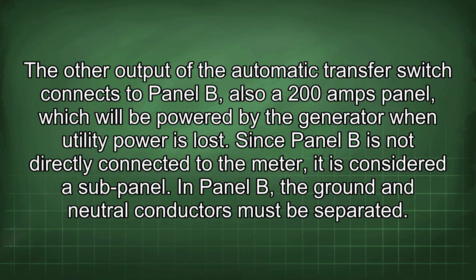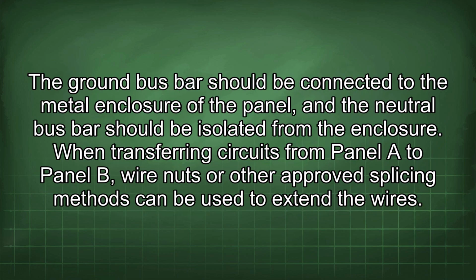Since panel B is not directly connected to the meter, it is considered a sub-panel. In panel B, the ground and neutral conductors must be separated. The ground bus bar should be connected to the metal enclosure of the panel, and the neutral bus bar should be isolated from the enclosure.